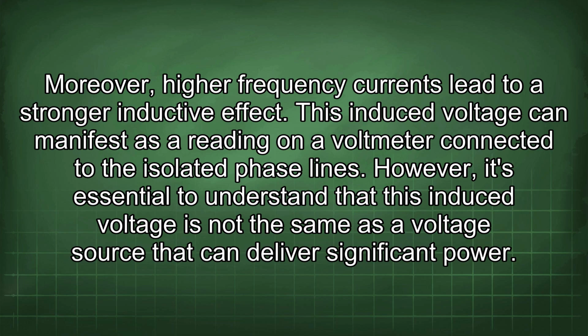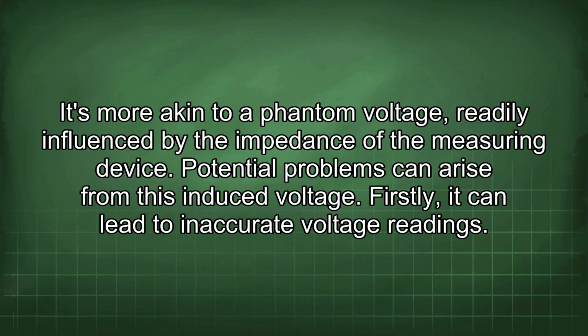This induced voltage can manifest as a reading on a voltmeter connected to the isolated phase lines. However, it's essential to understand that this induced voltage is not the same as a voltage source that can deliver significant power. It's more akin to a phantom voltage, readily influenced by the impedance of the measuring device. Potential problems can arise from this induced voltage.